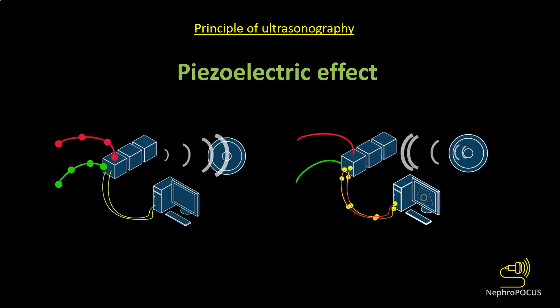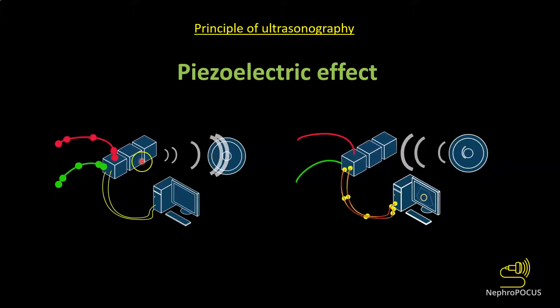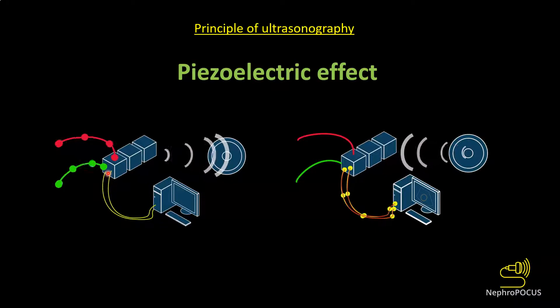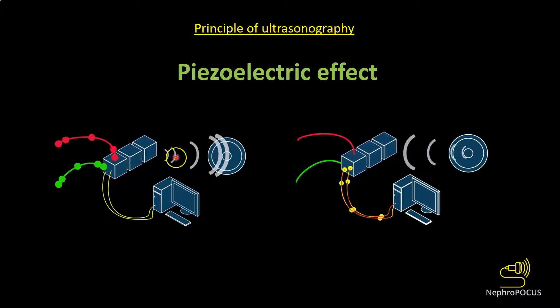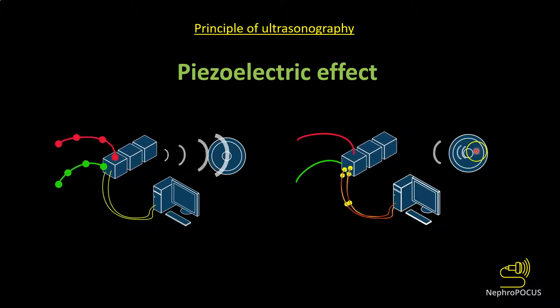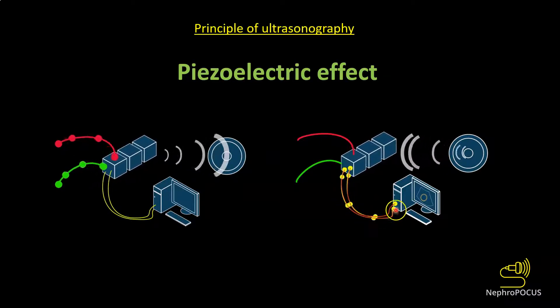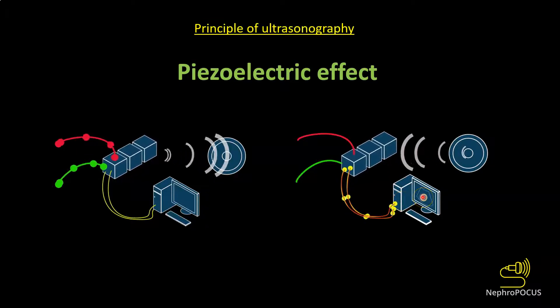The reverse piezoelectric effect is illustrated here. These are the piezoelectric crystals present in the ultrasound transducer. When stimulated by electrical impulses, they vibrate and produce ultrasound waves that hit the target organ. When the target organ makes echoes, those reflected sound waves stimulate the crystals again, generating electrical impulses which are processed by the ultrasound machine and displayed as an image on the monitor.